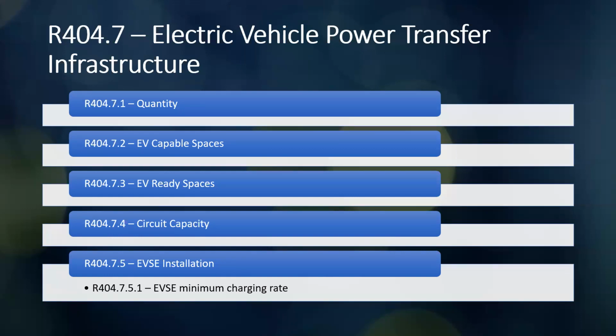It should either have EVSE or electrical vehicle supply equipment labeled. And then the circuit capacity, it's talking about the raceway is still saying if within 3 feet, and it's just talking about the equipment for that part of it that's in there. Sorry, I messed up. It's just the capacity of not less than 8.3 kVA or a 40 amp breaker at 208 or 240 volt for that space. And that repeats itself a lot in these requirements, is that 8.3 kVA or the 40 amps with 208 and 240 volts for that part of it.